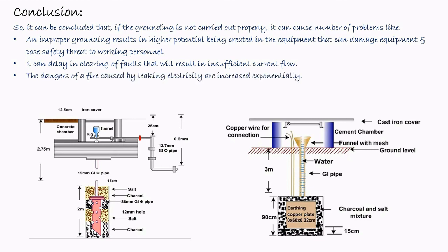The danger of a fire caused by leaking electricity is also increased exponentially because of the fault current, and if the grounding is not proper, then there may be a chance of fire also. It can cause a reduction in the operational efficiency of the machine as well, because if the fault current is more, the output of the system will be reduced, and therefore the overall efficiency of the system will also be hampered. Therefore, we can conclude that the earthing of the electrical system, both on the supply side as well as on the load side, should be proper. That's all. Thank you.